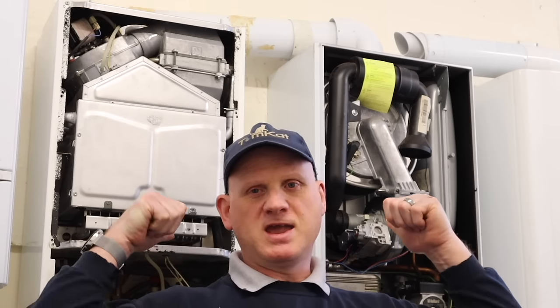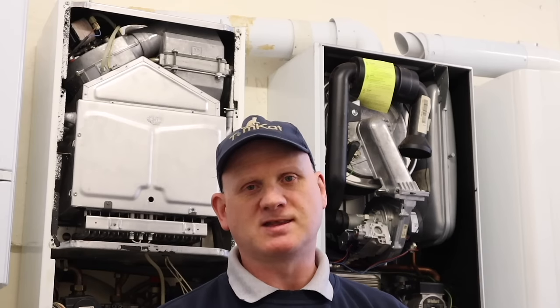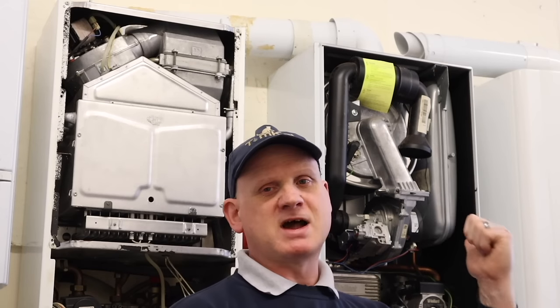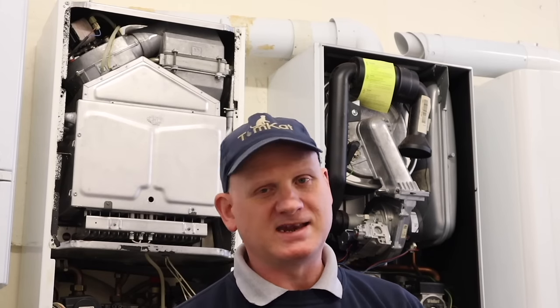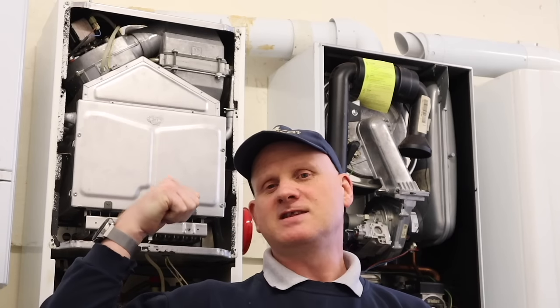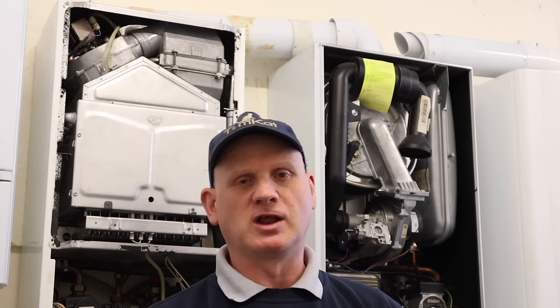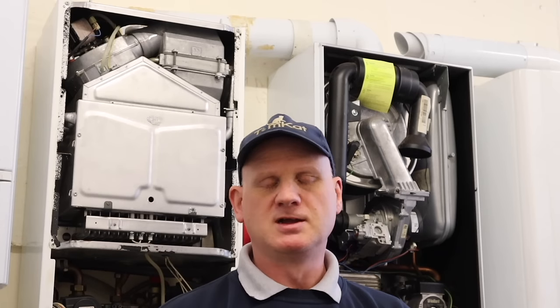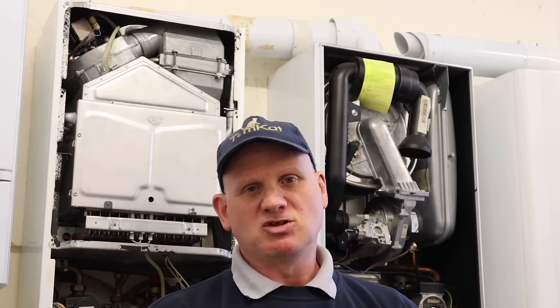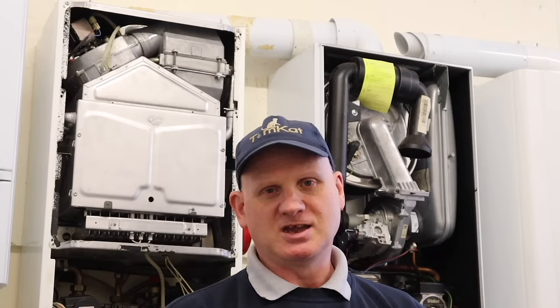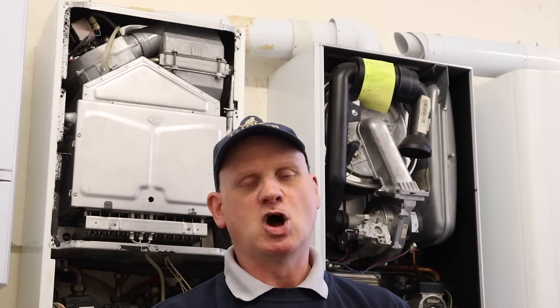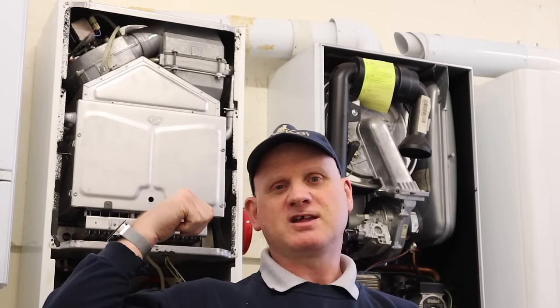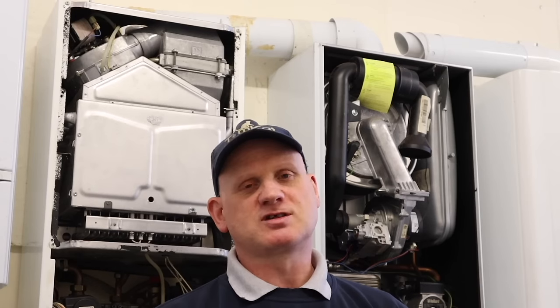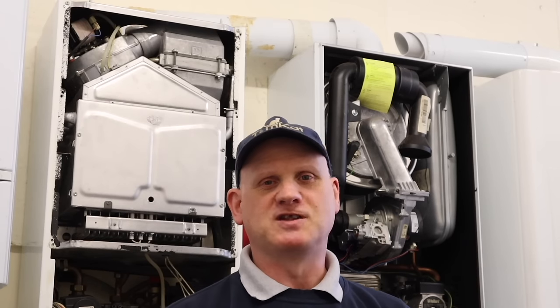Now, what I've got behind me here are two condensing boilers. This one to my left is one of the band A condensing boilers, and this is what we call the crossover boiler, where this was a band B boiler. This boiler has not been allowed to be installed since 2007 in the UK when we went to band A's only. So basically the manufacturers were given a couple of years to get rid of their old stock.